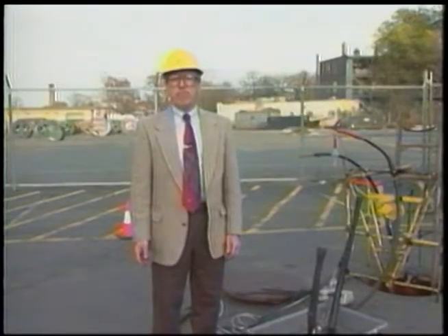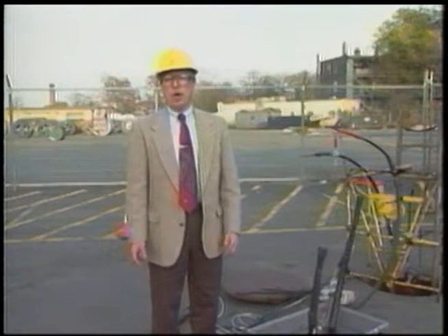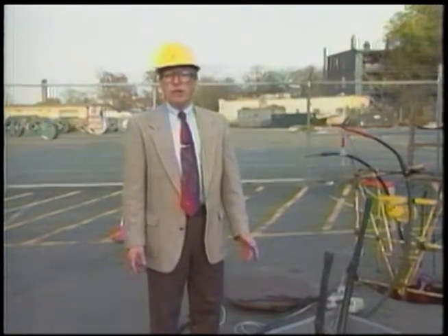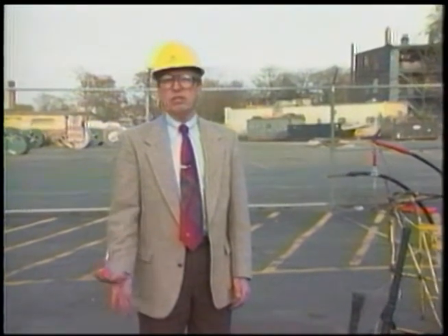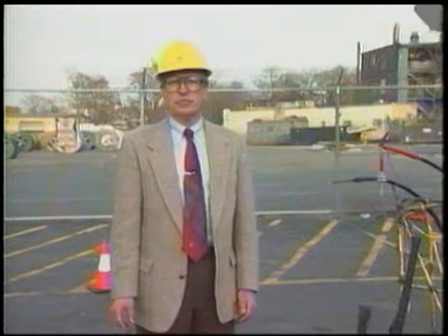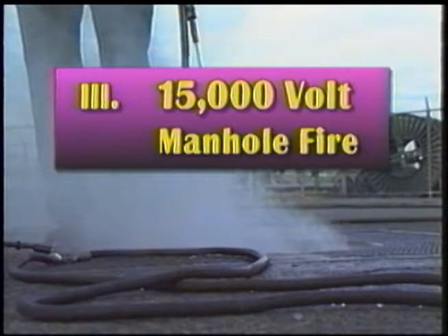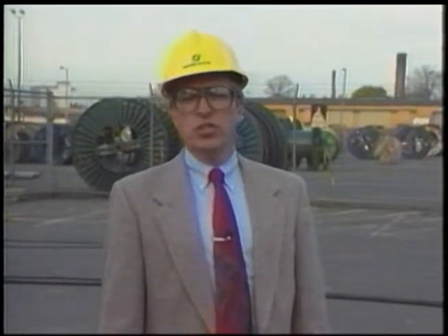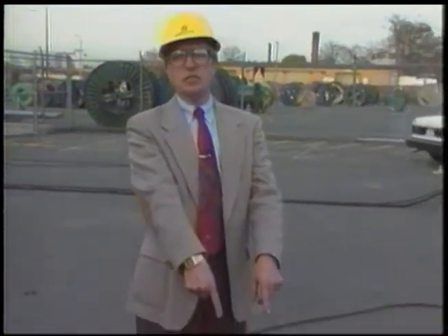We have just shown you a fault in air and in water. The fault in water is a solid body of water in which I put my hand in the water 12 inches away from the fault, and there was no danger of electrocution. This is the third demonstration. The 15,000 volt fault that you saw in air and in water, we now have placed inside this manhole.